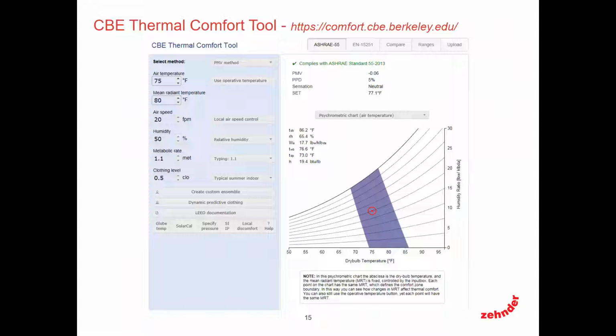California Berkeley also developed a tool that's online and available to everybody. I don't want to get into, and I'm not going to get into a lot of the detail on this, but it's a free tool out there that was sponsored by TC 6.5 and ASHRAE. And you could input your mean radiant temperature, your air velocity, operative temperatures. There's a number of factors in here that you can change over to determine whether you are compliant with ASHRAE 55. It's a very, very powerful tool when looking at not just radiant systems, but other systems too. So that's another reference out there for everybody.